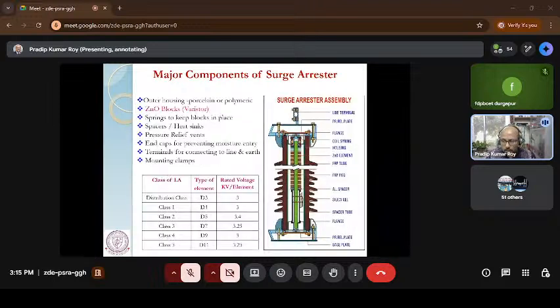So if I do the cross section, now the materials come in. You can see there are a number of blocks inside, stacked one after another. These blocks are actually ceramics. The outside periphery is the porcelain body, and inside that porcelain body, these ceramic blocks are available. This is called the varistor. The rest of the part is filled up by an aluminum tube. And here three things are very important. When I talk about the surge, it is a kind of impulse, a sudden attack. When this impulse immediately comes and hits the body, the material should have the capability to withstand that vibration. So above that block, there is a spring which sustains that vibration.